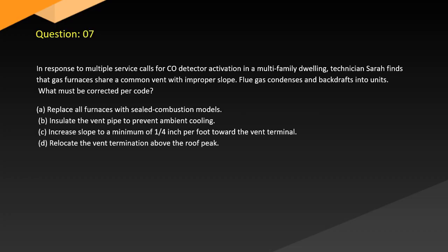Question 7. In response to multiple service calls for carbon monoxide detector activation in a multifamily dwelling, technician Sarah finds that gas furnaces share a common vent with improper slope. Flue gas condenses and backdrafts into units. What must be corrected per code?